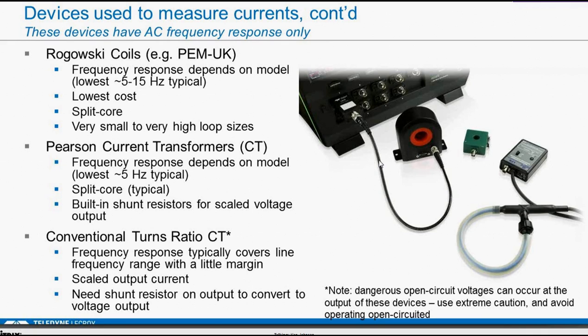Pearson's a company in the U.S., they make a Pearson current transformer. This has a voltage sense resistor built in, so it converts the current in the CT to a voltage signal, which is then very easy to put in another system. It saves a step. Or you could use a conventional turns ratio CT, which is really just a brute force core coil type design. And they have a current input through the center, and then it's a turns ratio with a current output proportional to the turns ratio.